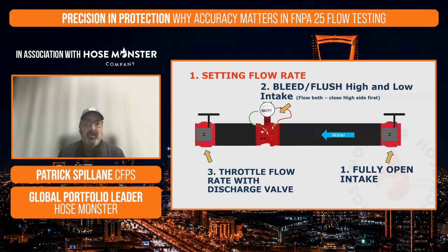So first, we're going to be talking about how to set our flow rate properly using a flow meter. All those installed flow meters should have two control valves before and after that flow meter. Again, we remember the intake side. This could vary per fire pump, depending on which direction the water is flowing. We want to make sure we understand the layout of that fire pump. Where's the discharge side of the fire pump? Where's the suction side? It's very important to making sure that we're reading that flow meter correctly. We also want to make sure that this gauge has been calibrated. We know it's going to be accurate because we just had it calibrated, as we do every year. We need to get this calibrated prior to our test.